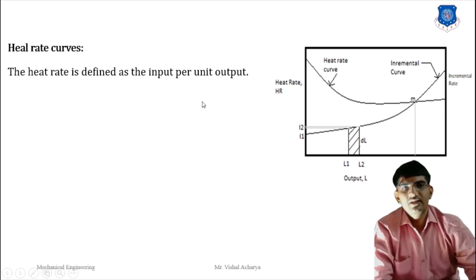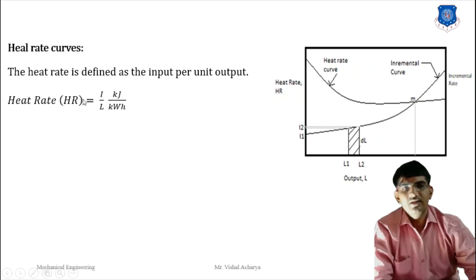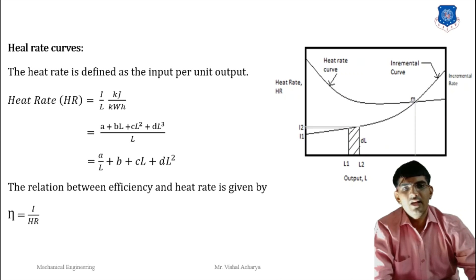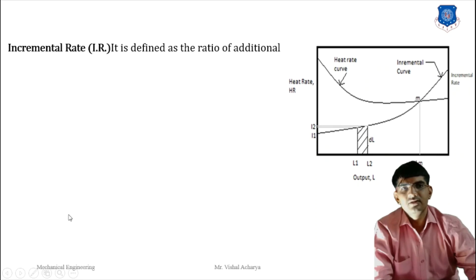Next is the heat rate. The heat rate is defined as the input per unit of heat output. As output increases, the heat rate first decreases and then becomes constant. Heat rate = input / output, with input in kilojoules and output in kilowatt-hours. So heat rate = (A + BL + CL² + DL³) / L = A/L + B + CL + DL². The relationship between heat rate and efficiency is that efficiency equals 1 divided by the heat rate — efficiency is the reciprocal of the heat rate.